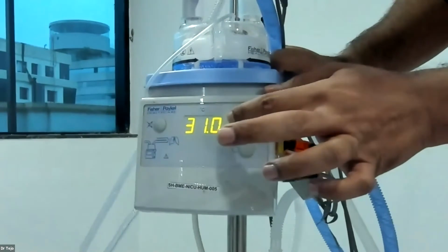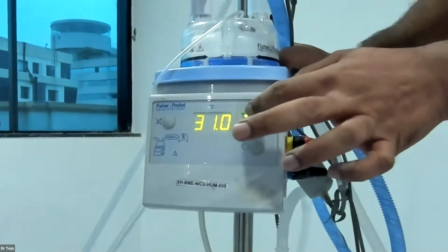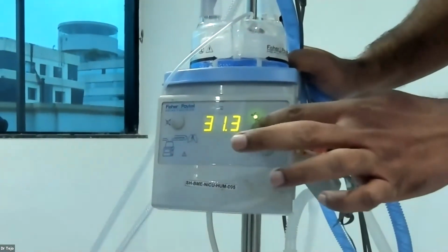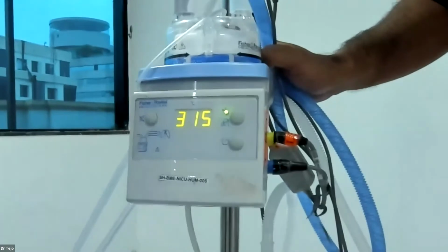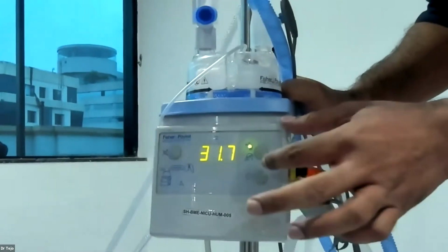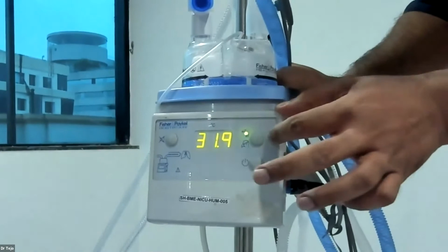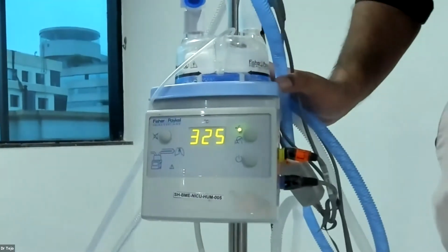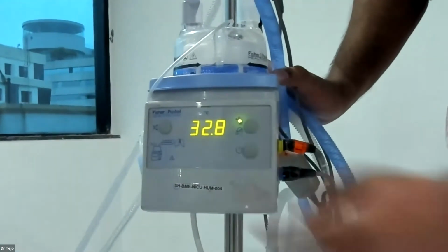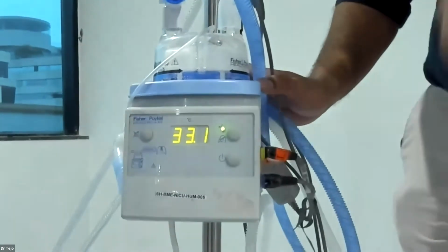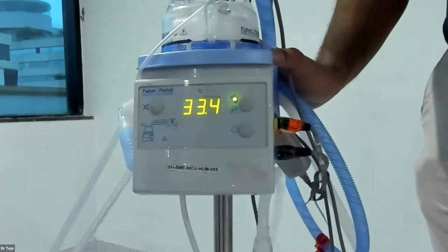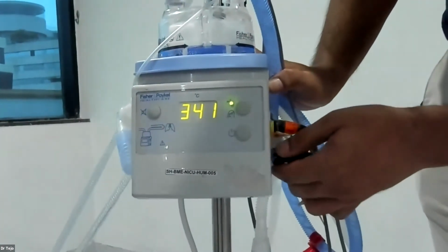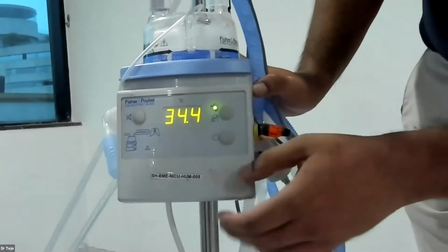The temperature in the invasive mode is usually 37, plus or minus 0.5, which will be calibrated by the software of this humidifier. In the non-invasive mode, it is around 31, up to a maximum of 34 degrees centigrade. 31 plus or minus 0.5 degrees centigrade is set in the humidifier software. There are 6 alarm systems. I can show you 1 or 2 here, and I will draw the diagram and show you the rest of the humidifier alarms. So you can see here 6 plus 1, 7 alarms are there.